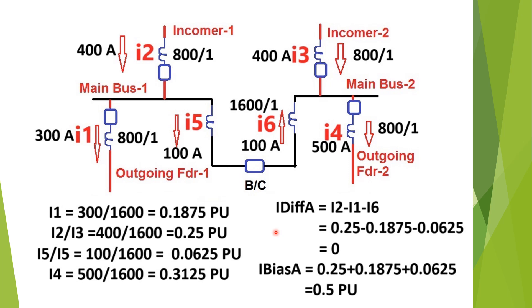For zone A, i_diff_A = i2 − i1 − i6 = 0.25 − 0.1875 − 0.0625 = 0. The bias current for zone A = i1 + i2 + i6 = 0.1875 + 0.25 + 0.0625 = 0.5 pu.